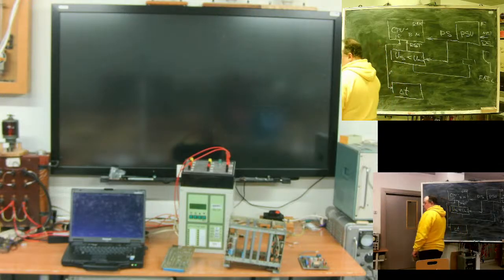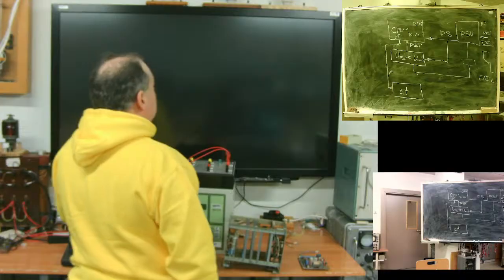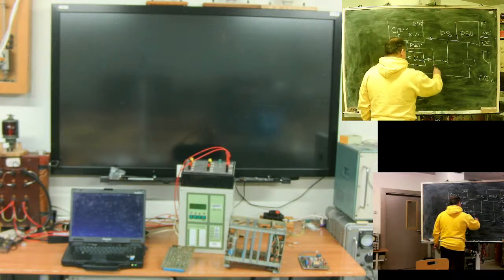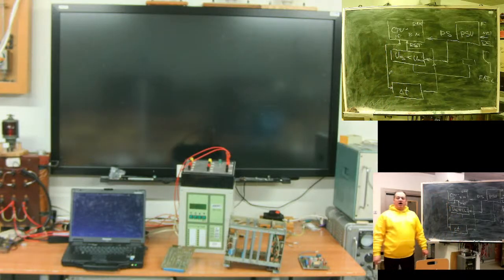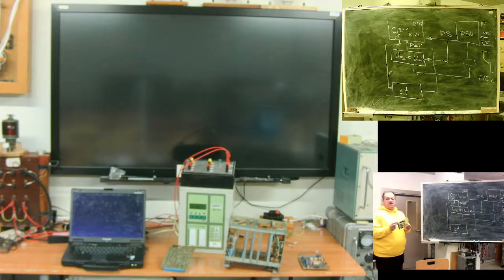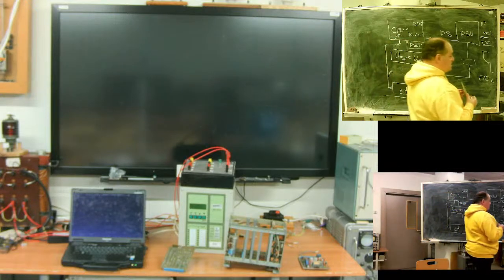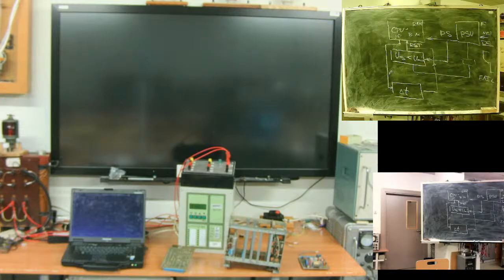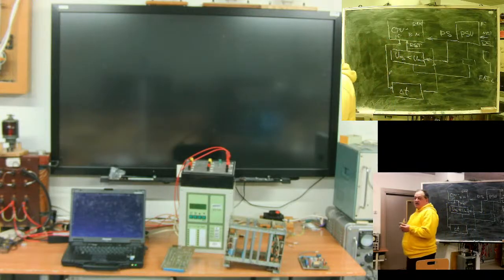From the CPU, the program code periodically sends a reset signal to this timer. In our case it's an external, absolutely independent timer. If the timer does not receive the signal within cycle time, here, if I remember correctly, within 2 milliseconds, the timer will produce a reset signal, a hardware reset signal. The CPU will receive a hard reset, all devices will receive a hard reset. Many designers call this test signal a heartbeat. So if the heartbeat signal is not received within 2 milliseconds of cycle time plus delay for timer operation, a hard reset signal is produced.